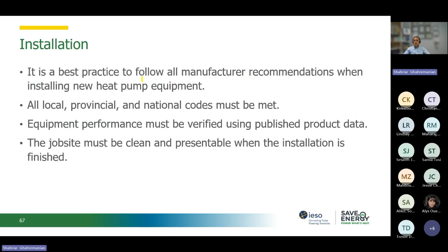For installation, it's best practice to follow the manufacturer's recommendation—that's the most important thing. The spec sheet provided by the manufacturer needs to be studied by designers to design a specific heat pump for the facility. All local, provincial, and national codes need to be met, and ASHRAE has lots of good standards for this. Equipment performance needs to be verified by published product data, and the job site needs to be ready for installation.